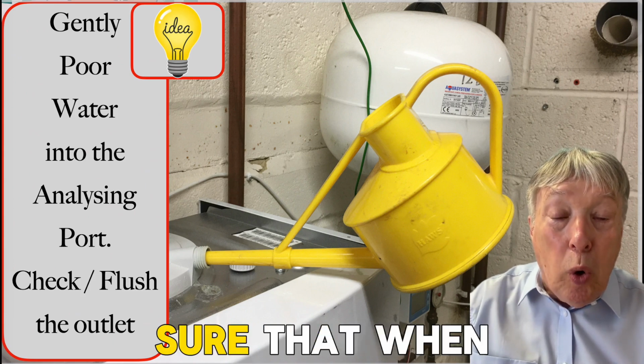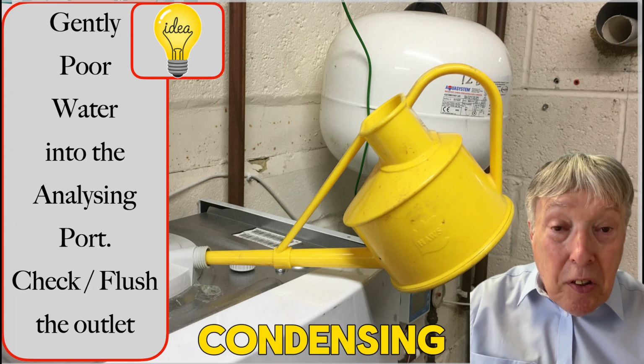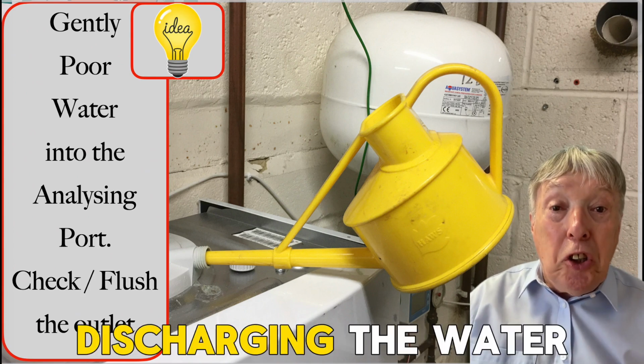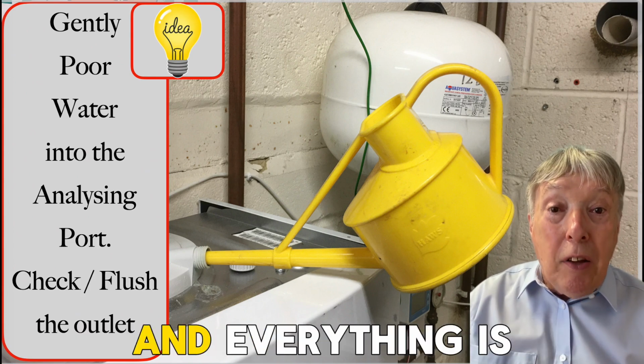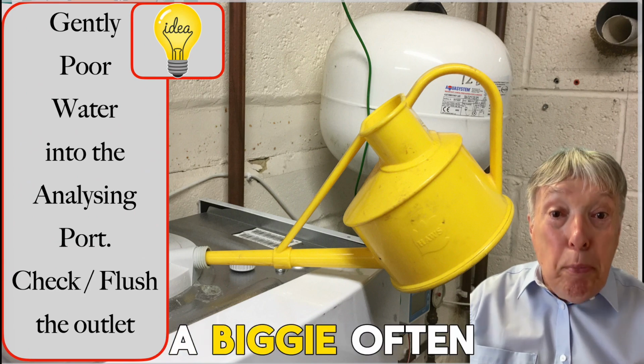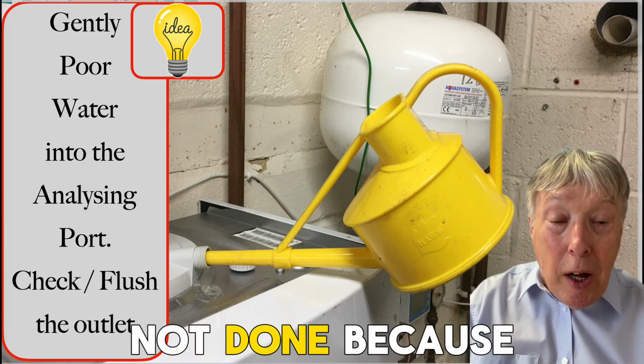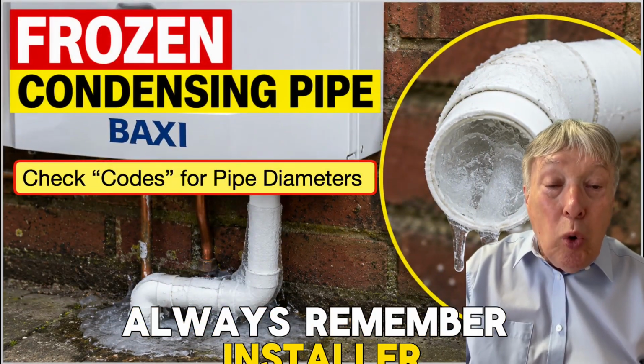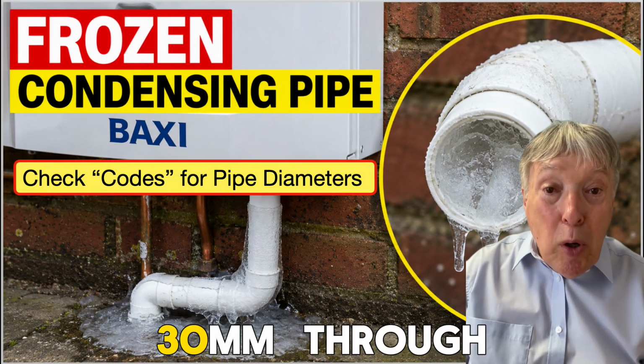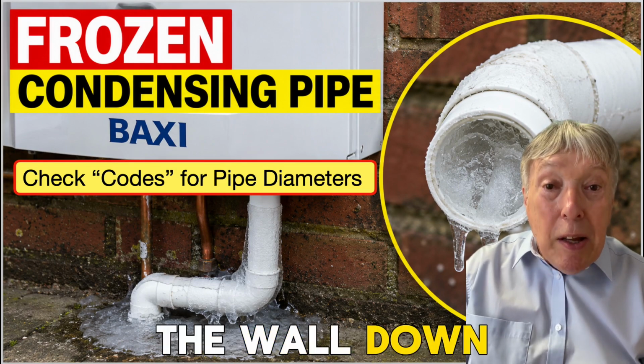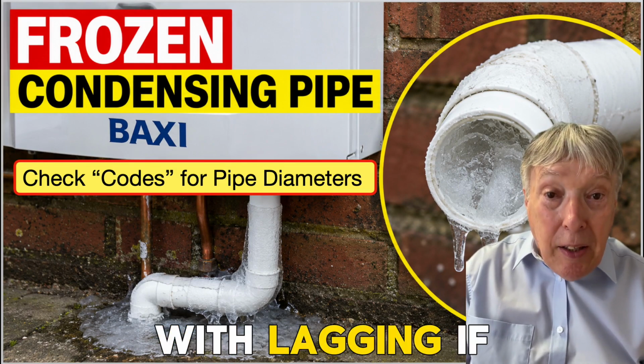So I make sure that when the boiler is condensing, it is actually discharging the water and everything is all right. So this is a biggie. Often not done because we forget. We tend to think. So always remember, installer, 30 mil through the wall down to the gully with lagging if necessary.